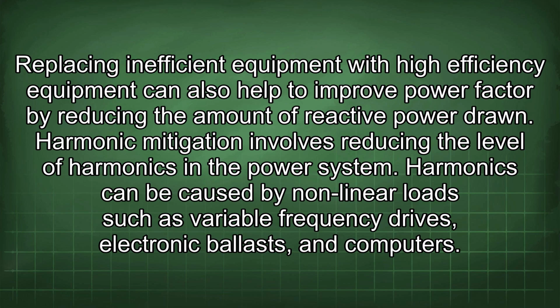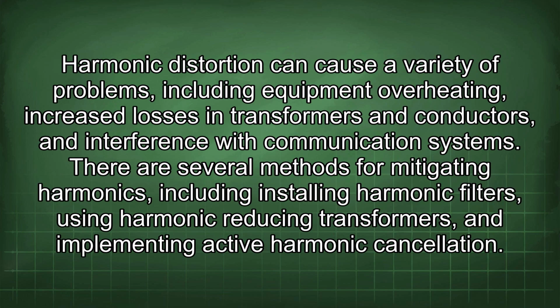Replacing inefficient equipment with high-efficiency equipment can also help to improve power factor by reducing the amount of reactive power drawn. Harmonic mitigation involves reducing the level of harmonics in the power system. Harmonics can be caused by nonlinear loads such as variable frequency drives, electronic ballasts, and computers. Harmonic distortion can cause a variety of problems, including equipment overheating, increased losses in transformers and conductors, and interference with communication systems.